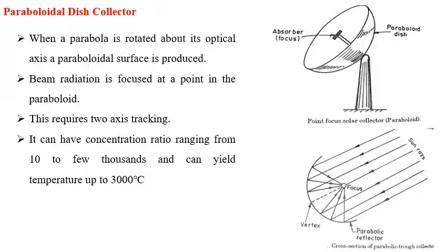The absorber located at the focus is a cavity made of a zirconium copper alloy with a black chrome selective coating. The heat transport fluid flows in and out of the absorber cavity through the pipes, which are bonded to the interior.